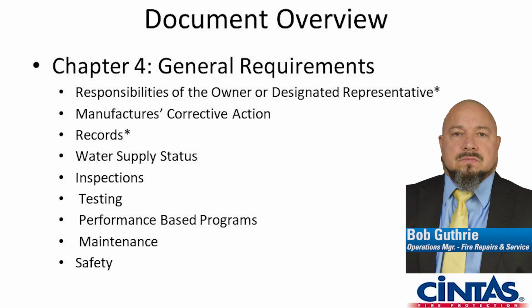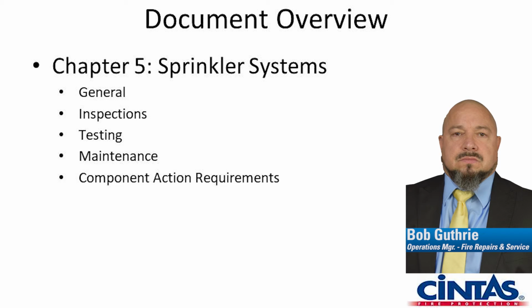Chapter 4 will be our general requirements, where we cover the responsibility of the owner or the designated representative, manufacturer's corrective actions, record keeping, water supply statuses, inspections, testing, performance-based programs, maintenance, and safety. Chapter 5 is specific to itself. The majority of Chapter 5 covers sprinklers, piping, more so sprinklers. That's the heaviest chapter for what we look for when we are conducting a sprinkler inspection. It gives us the dates and time periods a sprinkler can stay installed without any testing, and we'll cover a little bit more about testing of sprinkler heads in a minute. Maintenance and component action requirements.